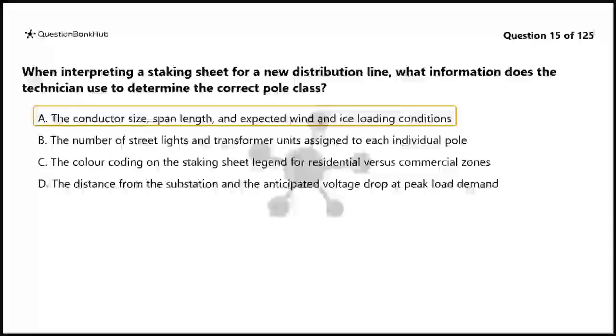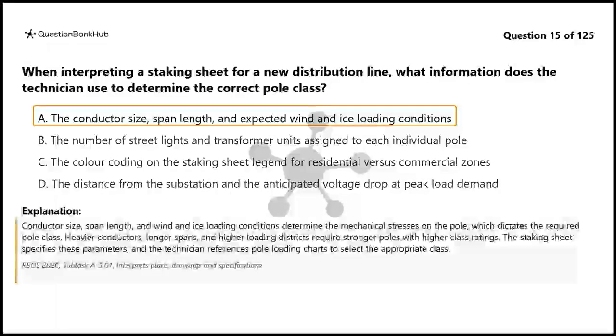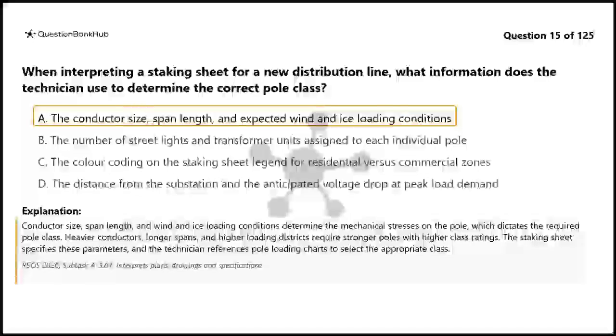The correct answer is A. Conductor size, span length, and wind and ice loading conditions determine the mechanical stresses on the pole, which dictates the required pole class. Heavier conductors, longer spans, and higher loading districts require stronger poles with higher class ratings. The staking sheet specifies these parameters, and the technician references pole loading charts to select the appropriate class.